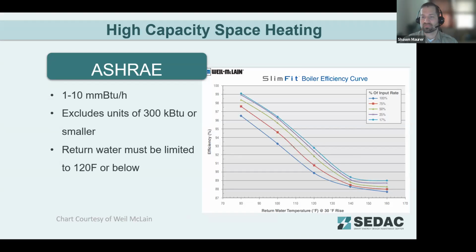ASHRAE also has specific requirements for high capacity space heating. Most new large boilers are condensing type boilers. The issue we run into with these is if the return temperature is too high for water coming back to the boiler, they can't operate in their condensing range and their efficiency is lost. And you essentially have a non-condensing boiler's operating efficiency, maxing out at about 85% for a system that's rated to have somewhere between 95 to 96% efficiency.